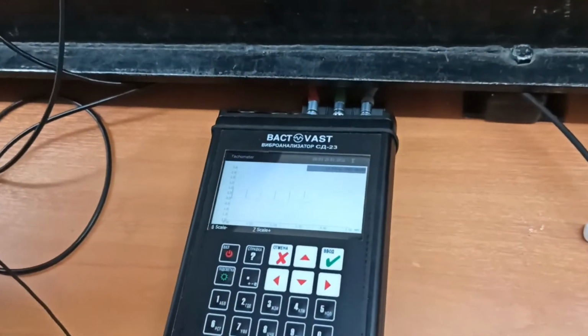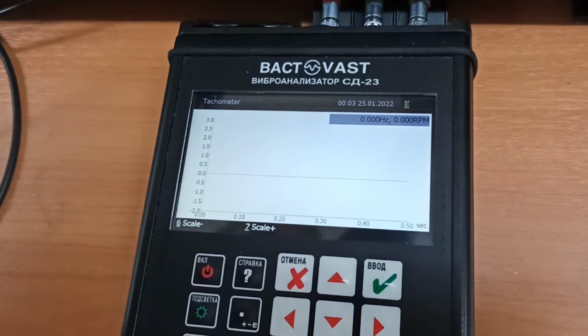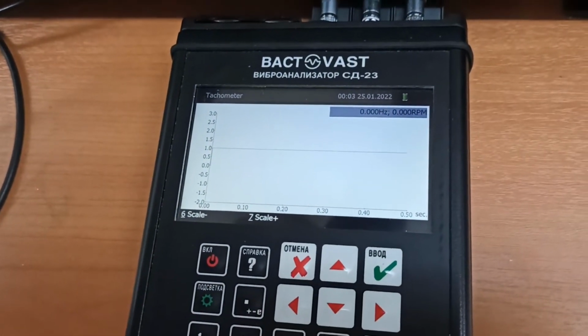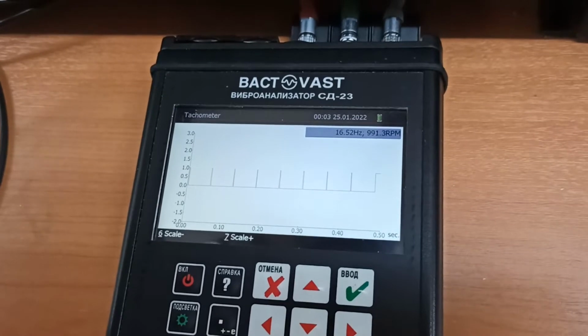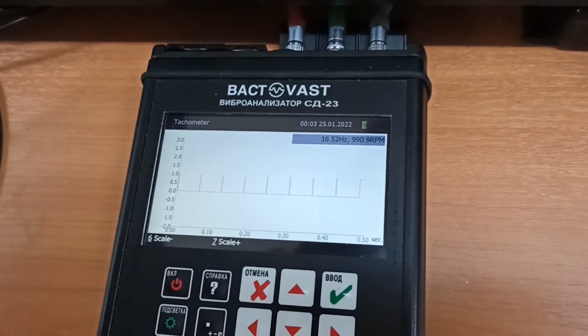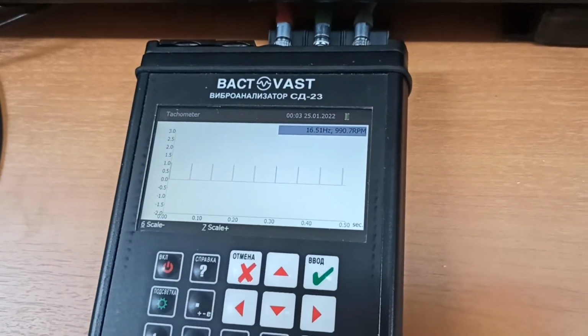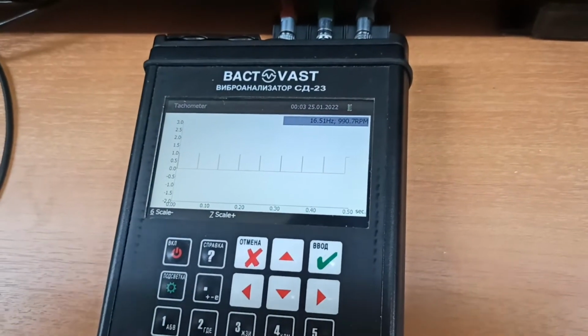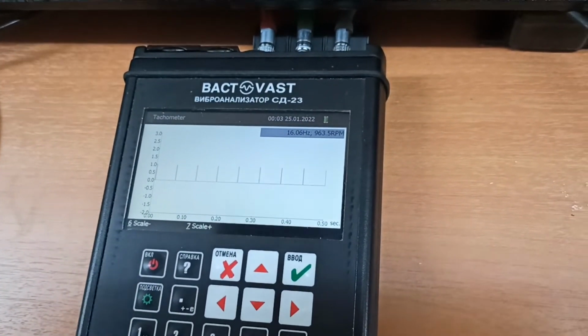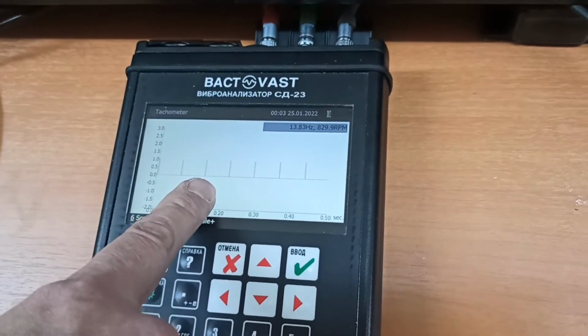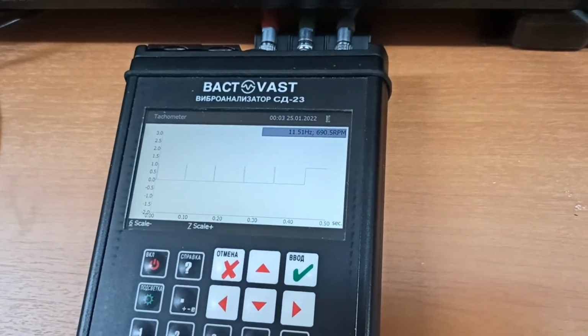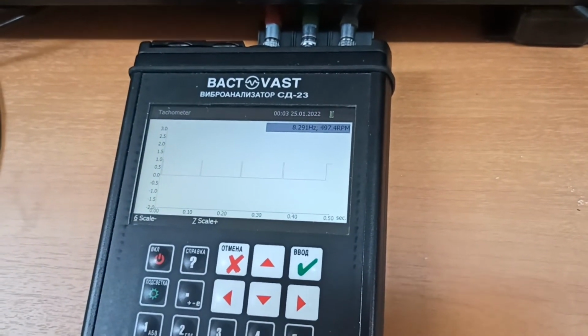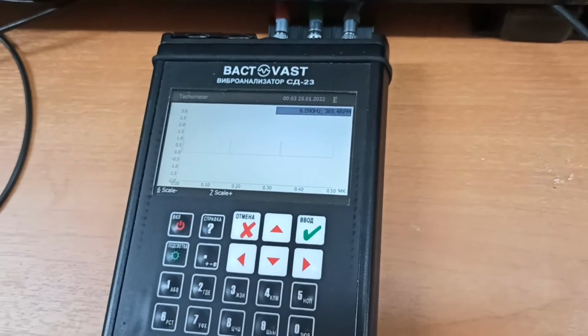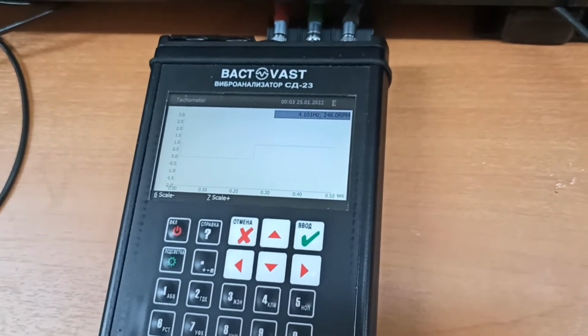If I move the tachometer somewhere away, it will not produce any mark. If I bring it to the right position, I get good marks. I fix my tachometer, and this is the tachometer installation. If I switch off my machine, you see that the rotation speed changes and it follows our rotation speed. So this is the sensor installation, and we are ready to start any job with the vibration analyzer.